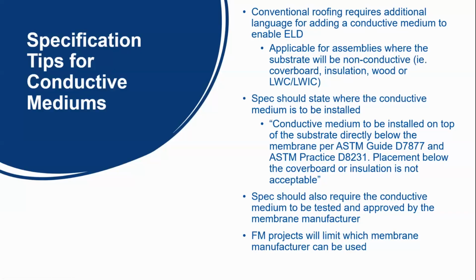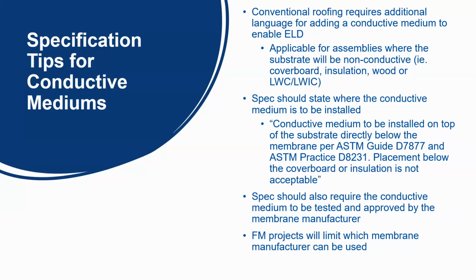Here's a quick spec tip for conductive mediums. Typically, conductive mediums are only needed in conventional roofing, so TPO, PVC, EPDM, mod bit, or any situation where the membrane is going directly to something non-conductive. Usually that's coverboard, might be insulation, could be wood or lightweight concrete. The spec needs to be very clear about where the conductive medium needs to go. That word directly is extremely important. That's what's found in the ASTM standards. That is the science and the physics of ELD.